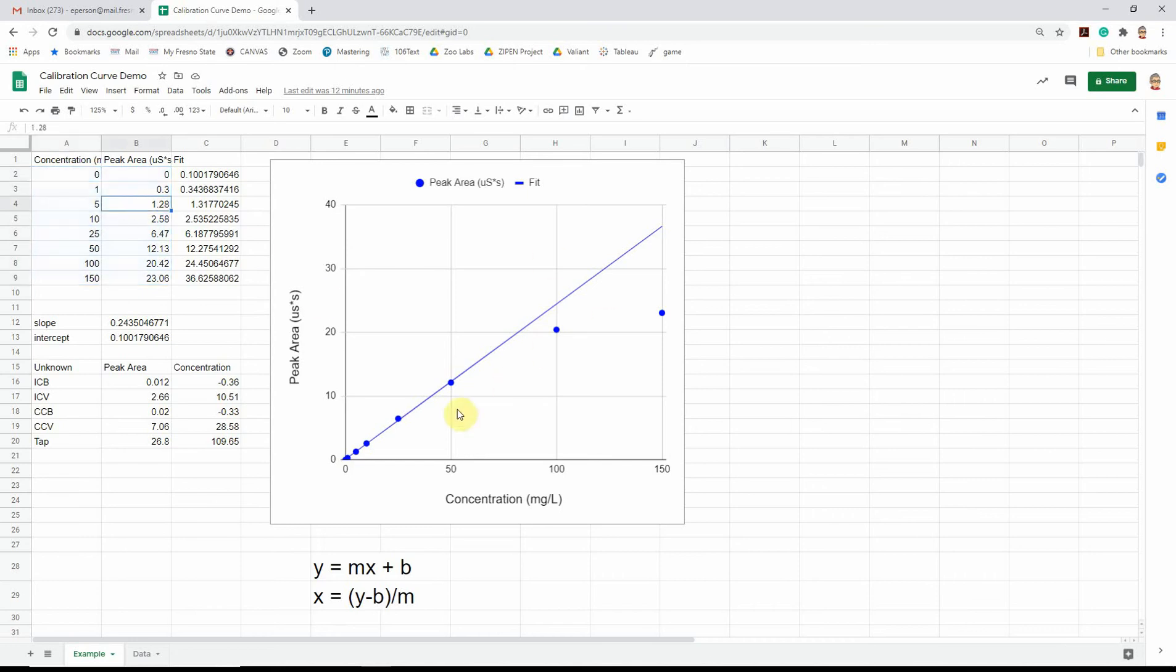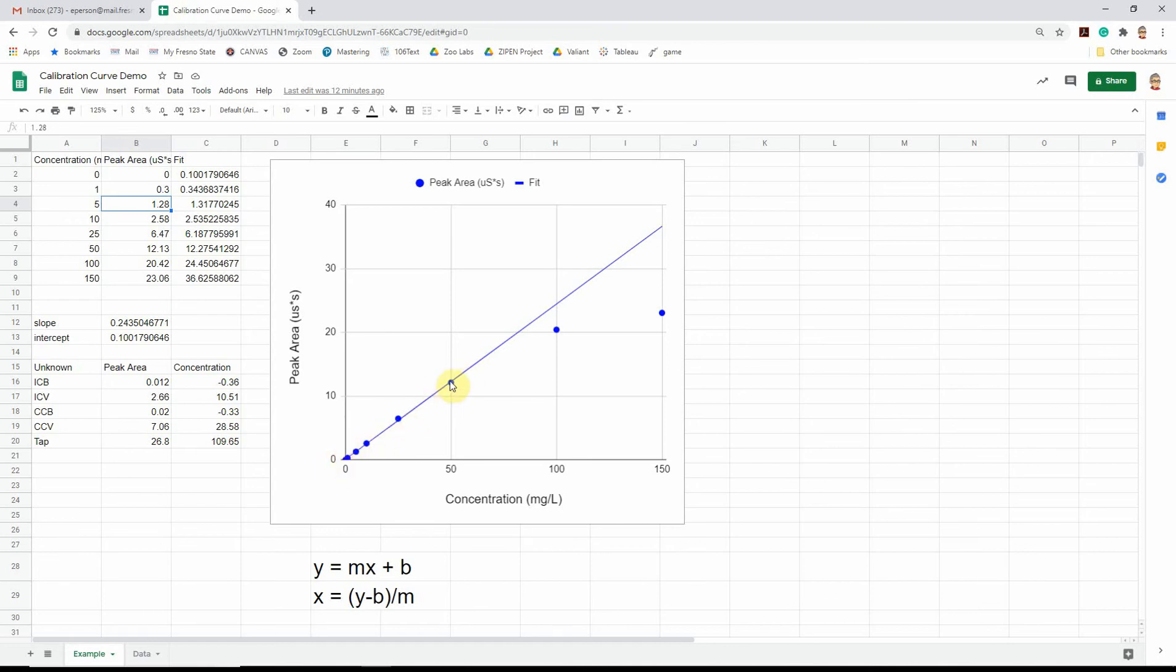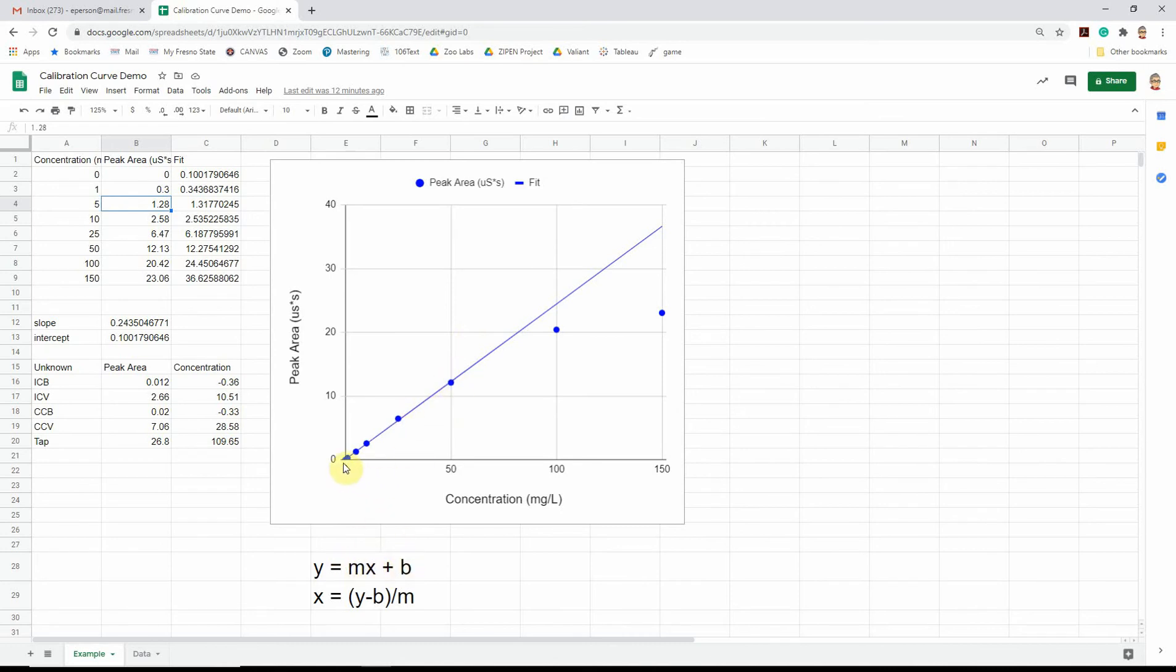We can take these data points and look for a region that's linear. You can do curve fits or some special fit algorithms, but most often we do calibration curves with linear data. And in this region here, the data is nice and linear and we can make a best fit line through there. And the math to do that's a little complex, but Excel and Google Sheets give us simple functions to do that. But basically what we do with that math is we figure out an equation for a line that best passes through our data.